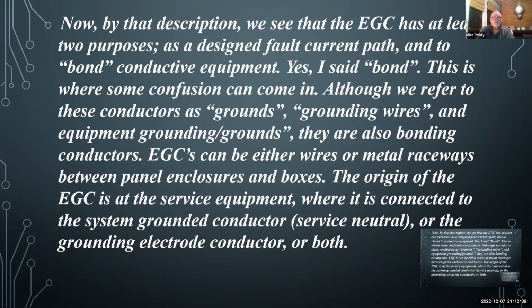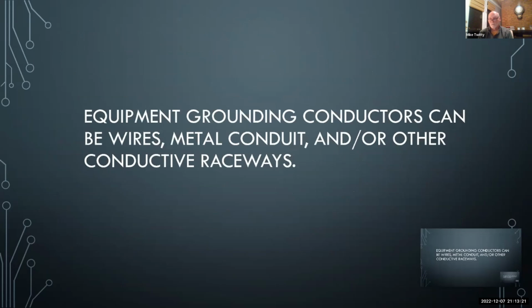They can be wires, they can be metal raceways between panels and enclosures and boxes. And the origin of it is always at service equipment, where it's connected to the service neutral and the grounding electrode conductor, or both. When I say that it can be raceways, metal flex can be used as an equipment ground, but not more than 6 feet. Metallic Sealtite flex, not more than 6 feet, but rigid, thin wall, intermediate metal conduit can all be used as equipment grounds. And sometimes it is. You'll see a panel and think something's wrong, and you say, well, I don't see an equipment ground feeding this panel. And then you look a little closer and it's got metal conduit, and that's being used as the equipment ground.